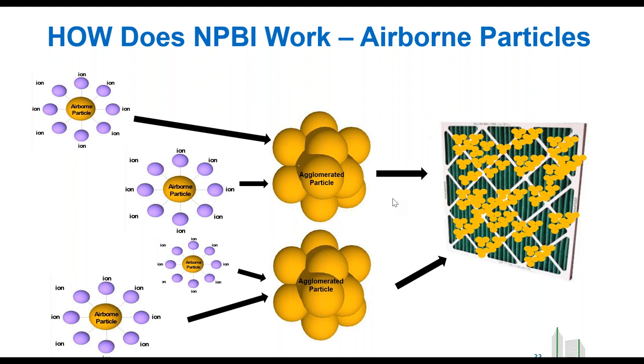Now that they're larger, they can actually be captured in the filter. Typically, those small particles previously bypass the filter. They land on the coil and they can grow into a biofilm. By agglomerating them and making them bigger, we can actually pick them up in the filter, and we're making the filter more effective and efficient. So by reducing airborne particles using agglomeration, we can reduce the transmission of viruses and pathogens in the air.